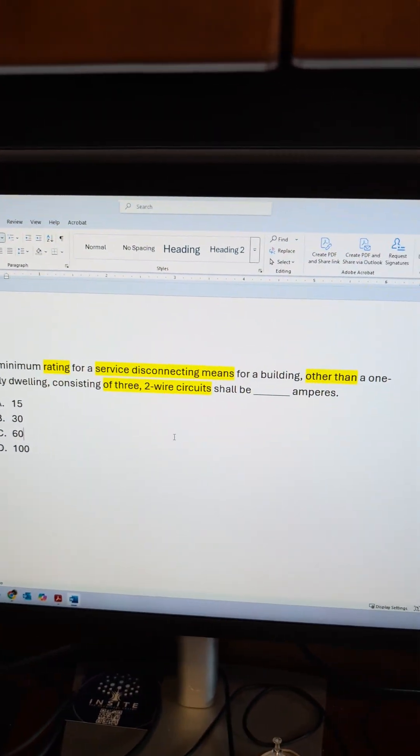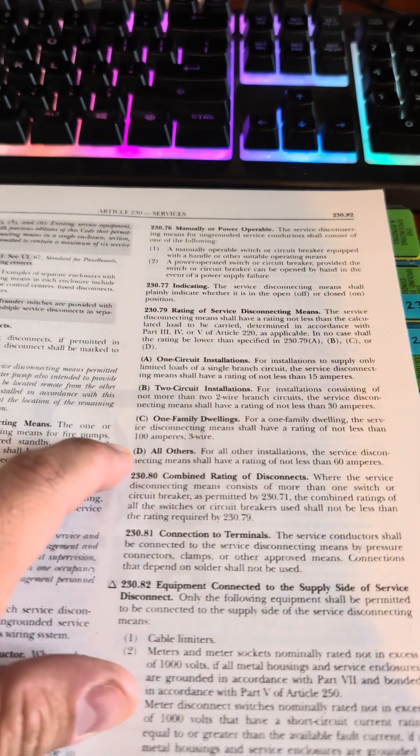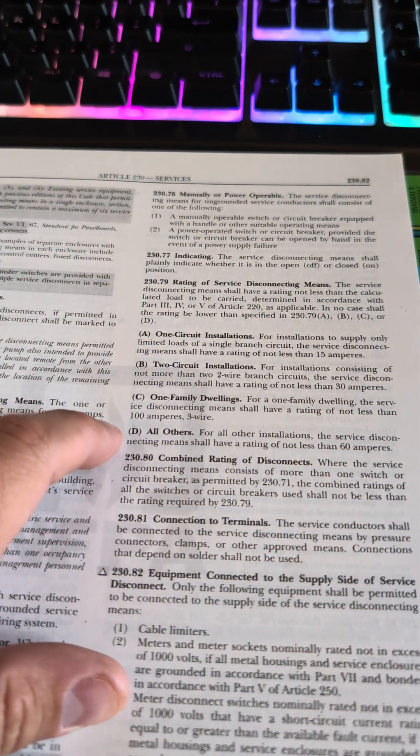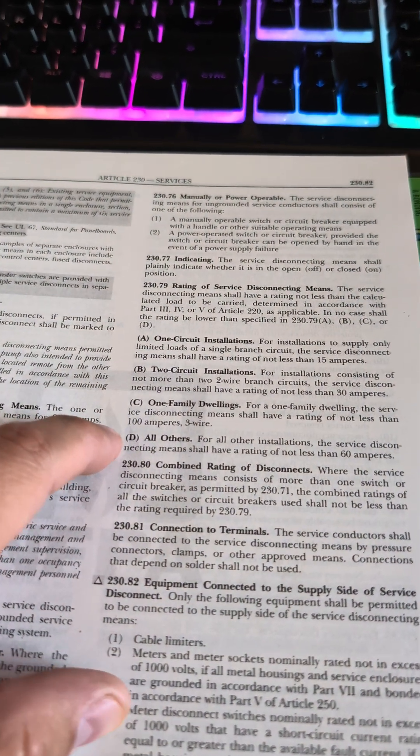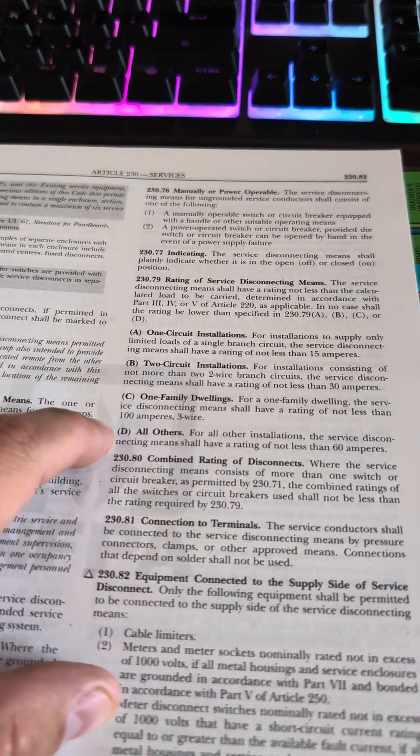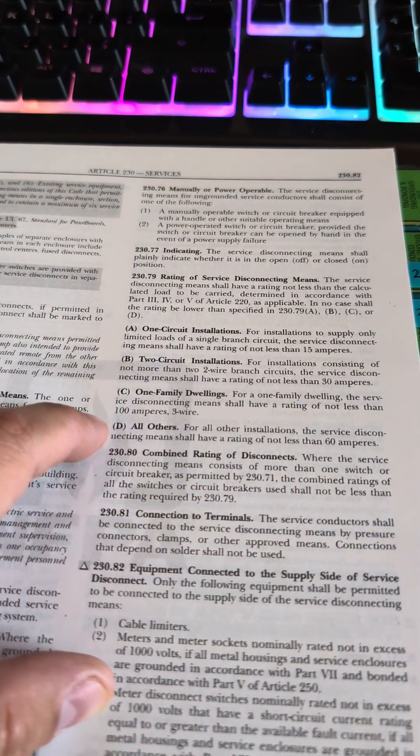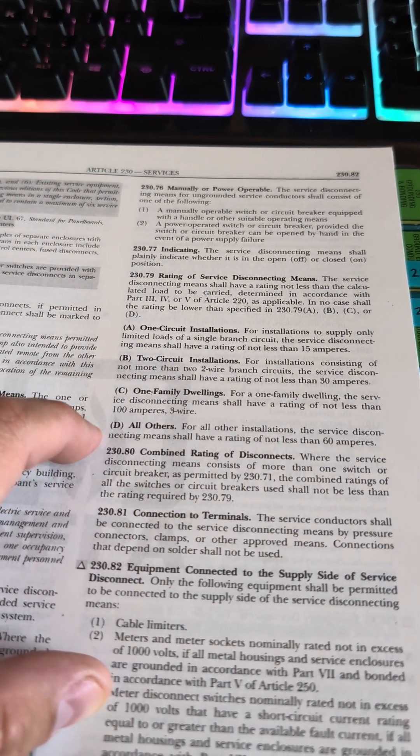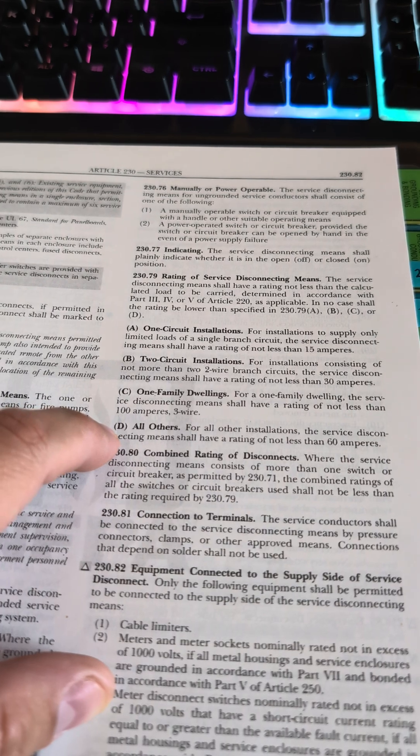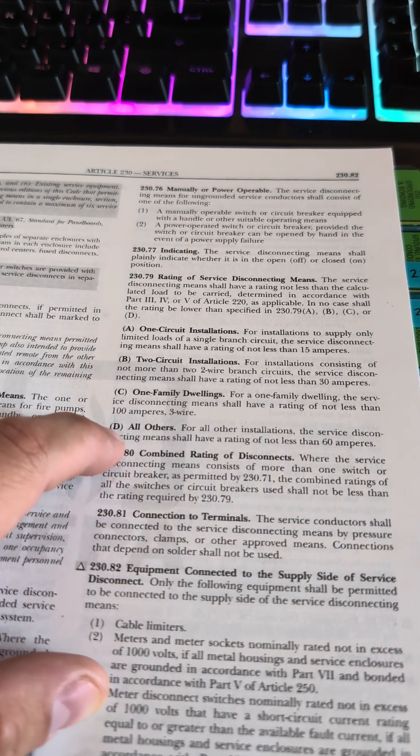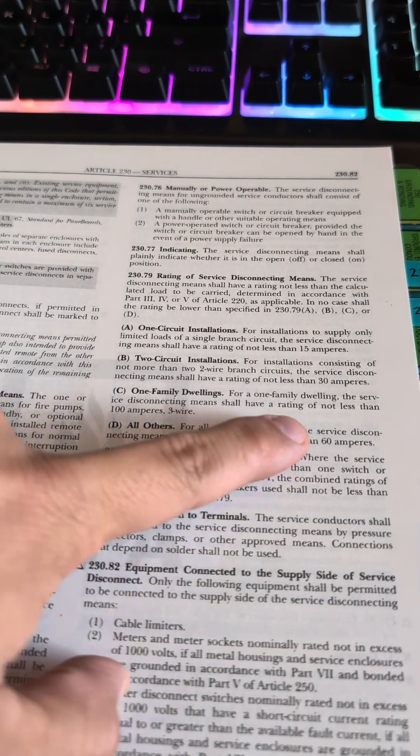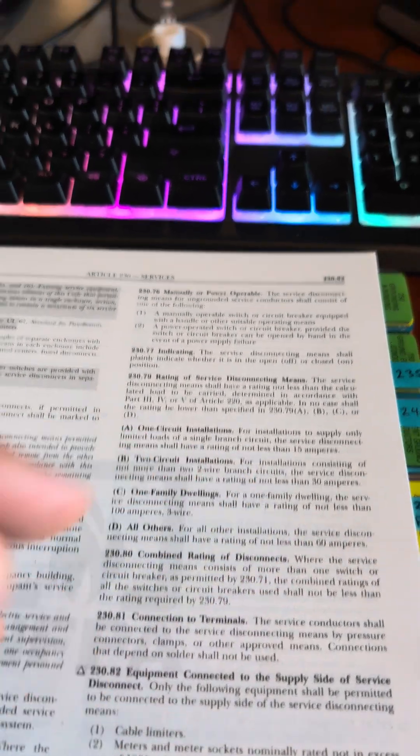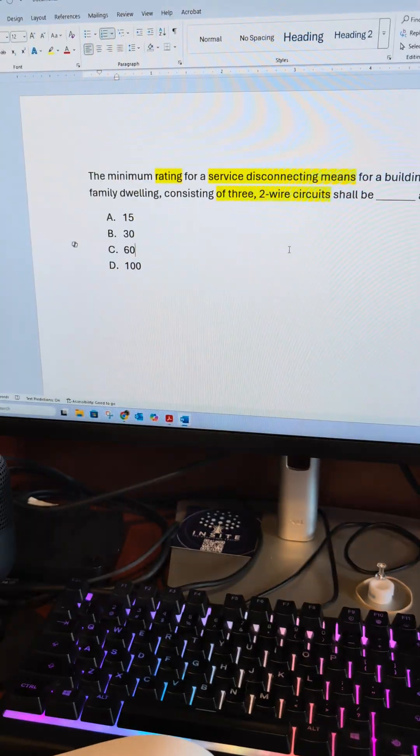Well, this is other than a one-family dwelling, so our only option is option D. For all other installations, the service disconnecting means shall have a rating of not less than 60 amperes.